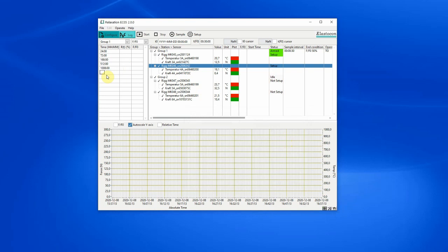Evaluation points can be specified. The evaluation values will be calculated as the test is running and can even be modified during the tests. The evaluation points are used when calculating results for the report.